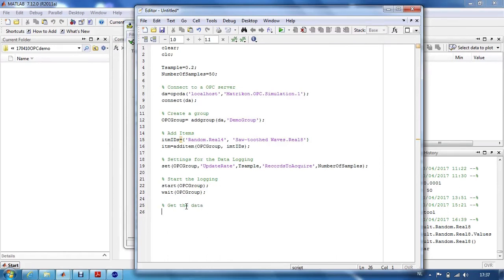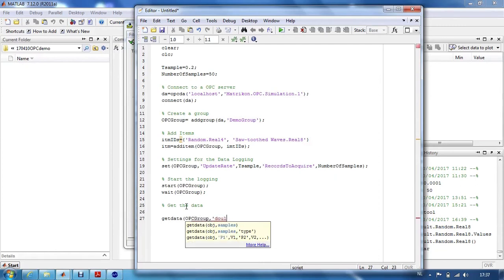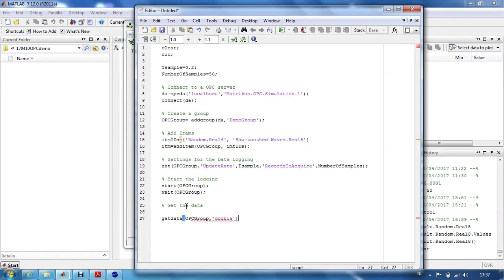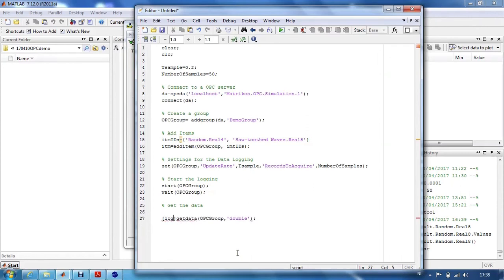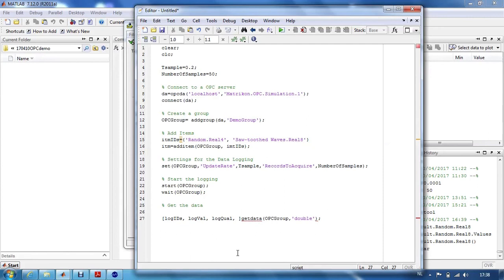Therefore, we use the command get data from the OPC group. We will import the data as double values. When we use this command get data, we get a lot of different arrays. First of all, we get the IDs of the logged data. We get the actual values, the quality, which is always included in OPC communication and is an indication for the communication quality. We get timestamps for each value.